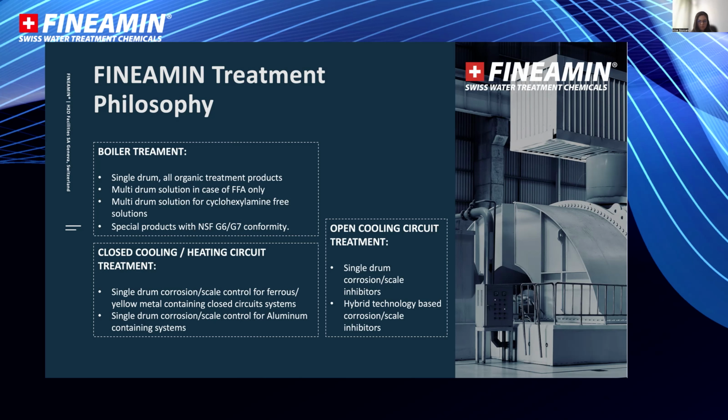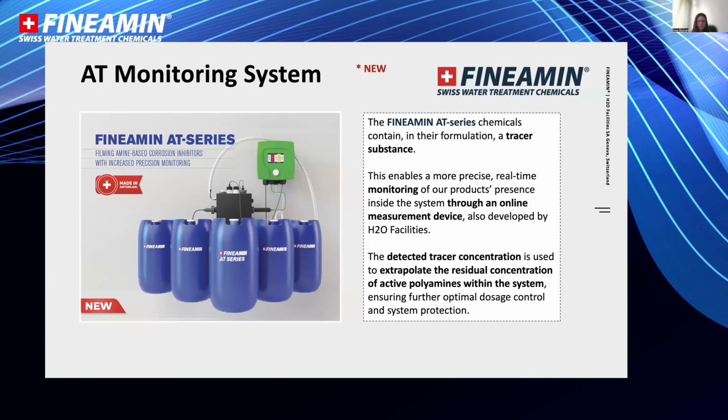And as I mentioned, for open cooling circuit treatment, we have single drum corrosion and scale inhibitors that should be complemented by biocides and any other chemical required for highly corrosive tendency waters, makeup waters. We also have hybrid technologies: corrosion and scale inhibitors, film-forming amine, along with environmentally friendly phosphonates. Not only this, but we also have special products that contain a tracer. That fluorescein molecule can be measured after the dosing, ensuring automation of the product dosing to the system.